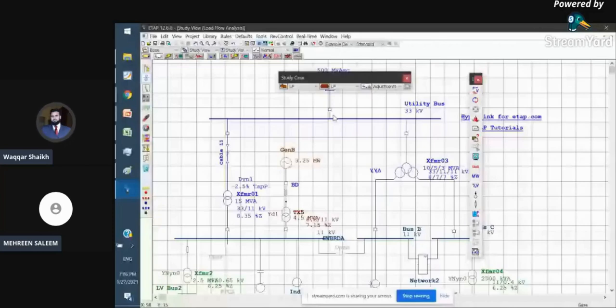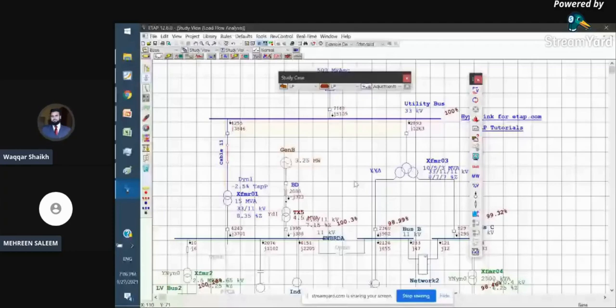In load flow study, we're normally interested in finding bus voltages, line currents, active and reactive power flows, and cable voltage drops. We check whether equipment ratings are as required by the load flow results or not — sometimes transformers or cables can be found overloaded. So we fine-tune those components, or rearrange the load configurations, to bring the results within acceptable limits.